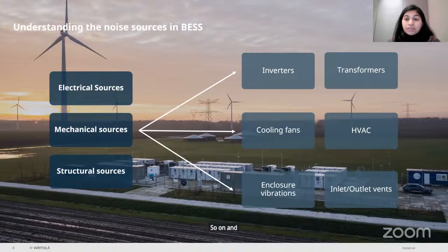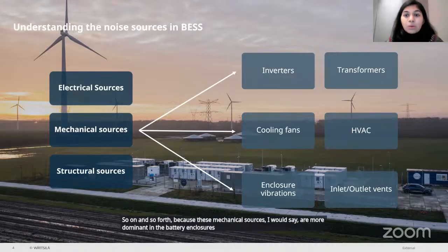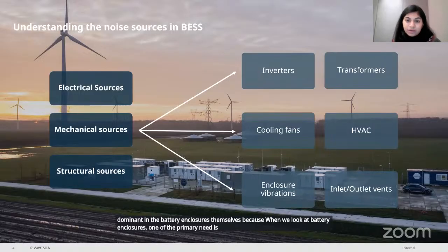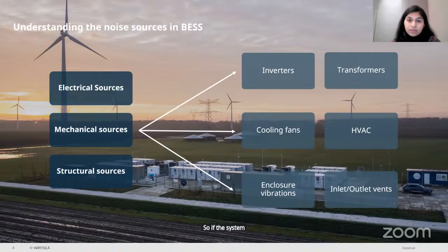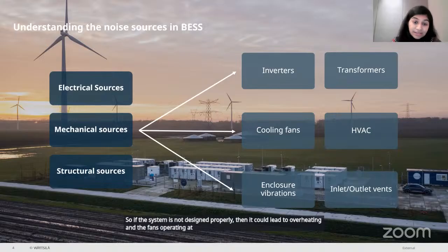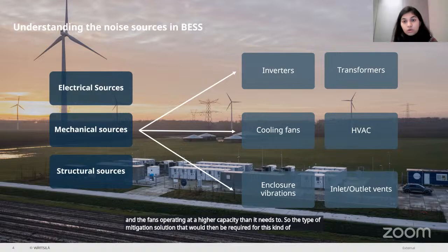Because these mechanical sources are more dominant in the battery enclosures themselves. When we look at battery enclosures, one of the primary needs is thermal management and the cooling system to avoid overheating issues. So if the system is not designed properly, it could lead to overheating and the fans operating at a higher capacity than needed. So the type of mitigation solution required for this kind of noise would look much different.